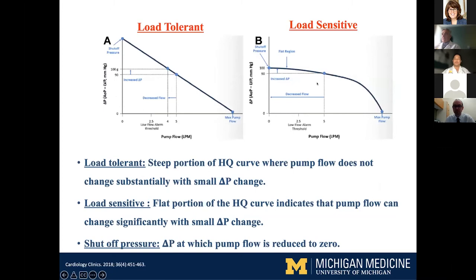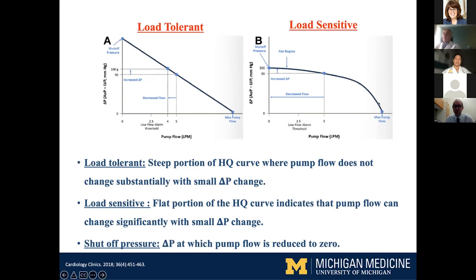At the lower ranges of flow, the HeartMate 3 is load-sensitive, so a small change in the difference between aortic and LV pressure — the afterload versus preload — can cause a bigger drop in flow. Whereas out at higher flow ranges, it's more resilient. We really want to keep the flow in that outer working range.